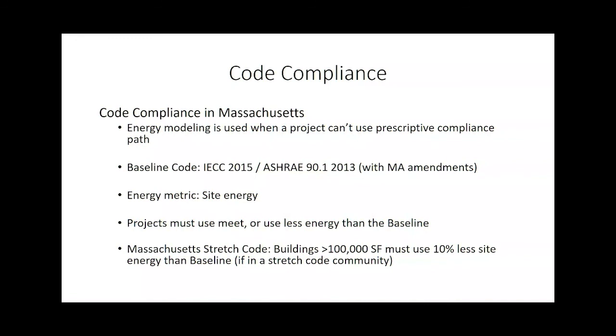If one of those items is not in prescriptive compliance - say you wanted to use inefficient chillers, or more likely your wall assembly couldn't quite meet the requirement, or most often, the code requires a maximum 40% window to wall ratio, and most office and residential buildings built these days have a higher ratio - then you can no longer use prescriptive compliance, so you have to use an energy model. With code compliance, you just have to show that your building uses the same amount or less energy than a code compliant version of your building.